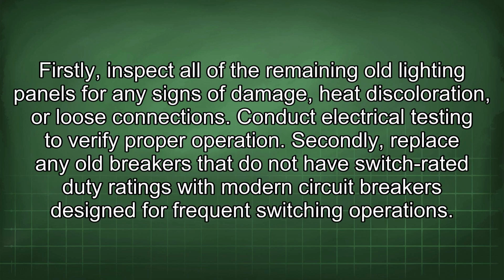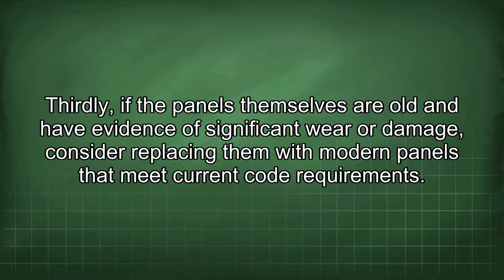Firstly, inspect all of the remaining old lighting panels for any signs of damage, heat discoloration, or loose connections. Conduct electrical testing to verify proper operation. Secondly, replace any old breakers that do not have switch-rated duty ratings with modern circuit breakers designed for frequent switching operations. Thirdly, if the panels themselves are old and have evidence of significant wear or damage, consider replacing them with modern panels that meet current code requirements.